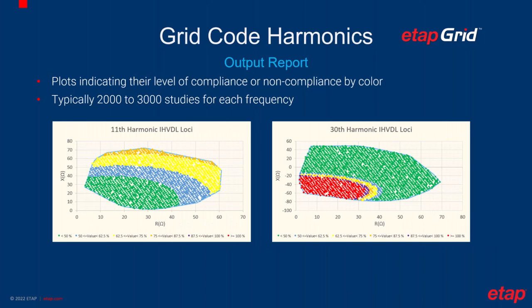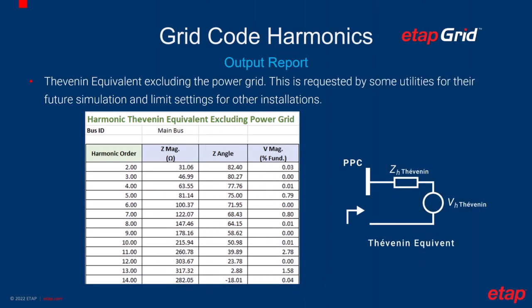The results impedance loci tab in the Excel report includes a set of graphical outputs with color coding. The color coding indicates, for each calculated sample impedance point, how far the incremental distortion is from the limit. The Thevenin Equivalent tab of the report provides the Thevenin impedance, the impedance angle, and the voltage magnitude at the point of common coupling, excluding the impact of the power grid. This data helps the utilities with future simulations and the limit settings for other installations. Some grid codes will require this information as part of the application.